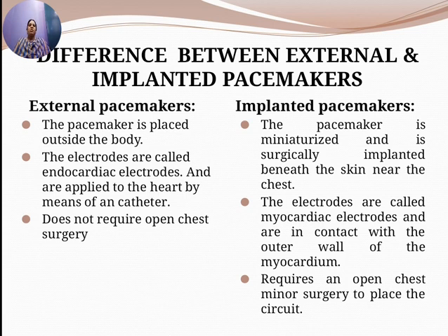The electrodes used in external pacemakers are called endocardiac electrodes and are applied to the heart by means of an electrode catheter. You are going to use a catheter with the electrode tip situated in the apex of the heart ventricle. They are in contact with the inner surface of the heart chamber. Whereas in internal or implanted pacemakers, the electrodes are myocardiac electrodes and are in contact with the outer wall of the myocardium.